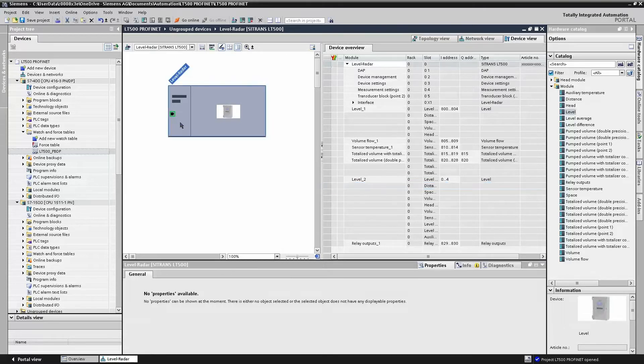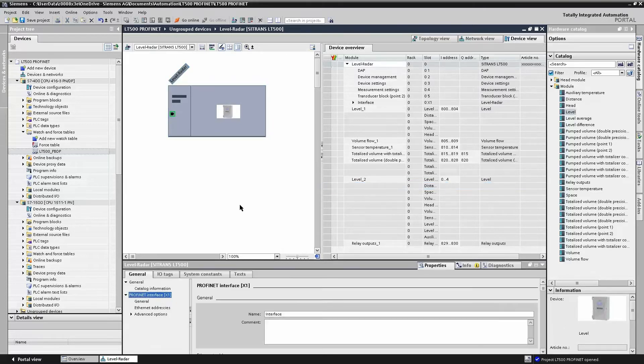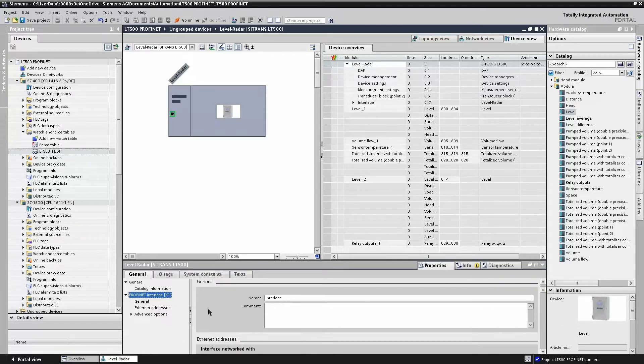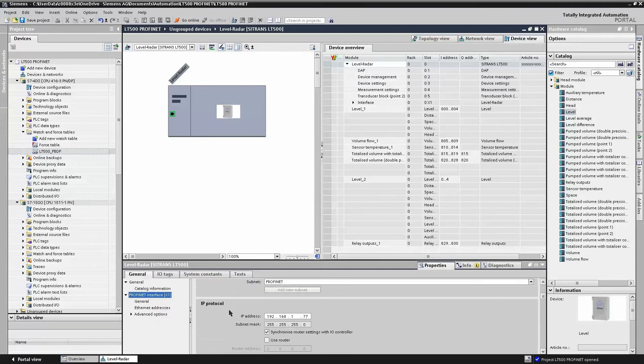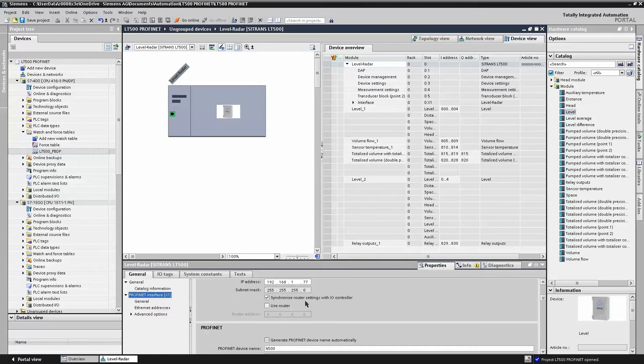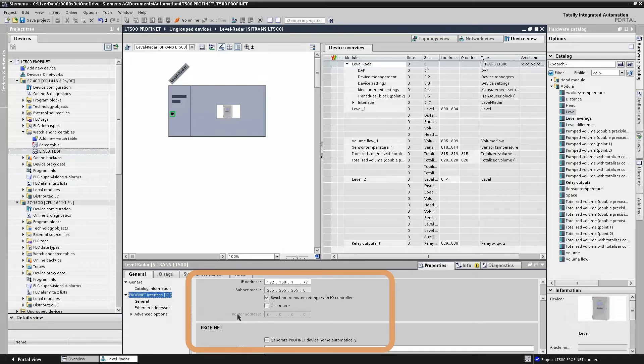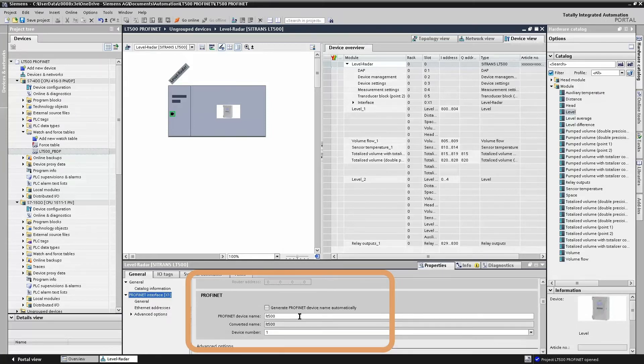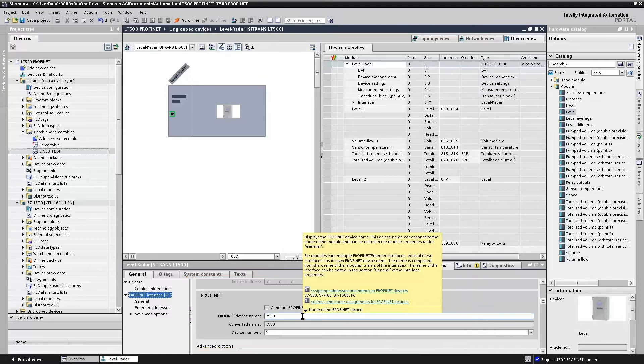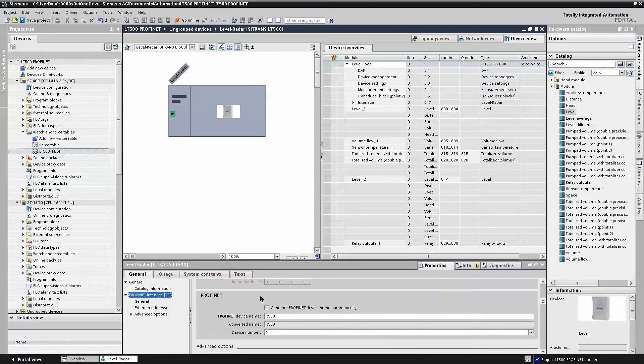All that's required to do next is to add the IP address and the device name. So if we look at the LT500 properties, we enter the IP address and we enter the device name. The device name will be used by the IO controller to identify the LT500, and then the IO controller will issue the IP address.